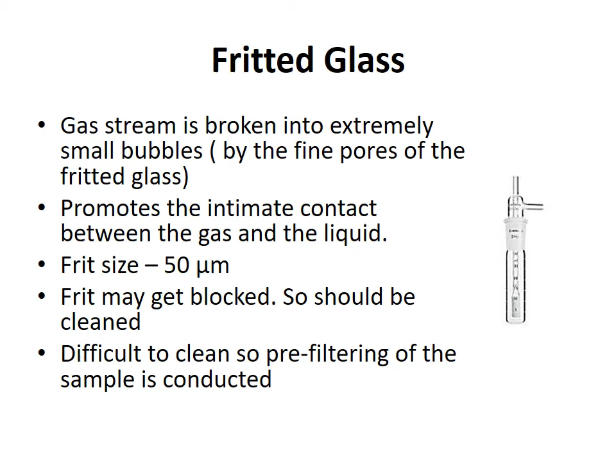Fritted glass. In this, the gas stream is broken into extremely small bubbles by the fine pores of the fritted glass. It promotes the intimate contact between the gas and the liquid. The frit size is about 50 micrometer. The frit may get blocked, so it should be cleaned regularly. It is difficult to clean, so pre-filtering of the sample has to be done.